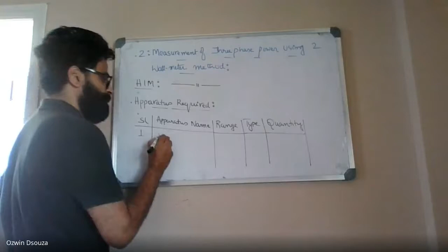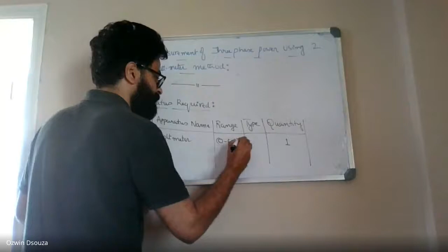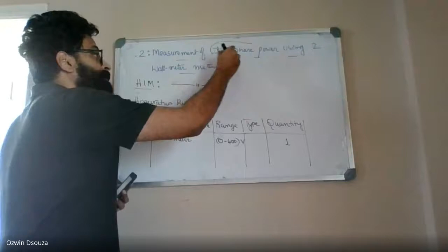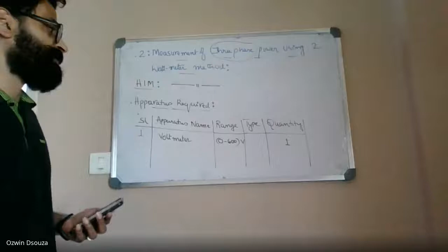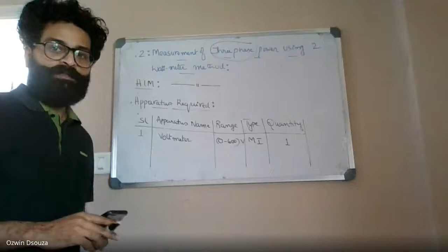So, voltmeter: you would need 1 voltmeter of the range 0 to 600 volts. Why 0 to 600 volts? Because you are connecting to a 3-phase supply, and the magnitude of 3-phase supply is about 415 volts, so the nearest scale value is 600. That's how we select the range: 600 volts, and type is MI, moving iron, because it's an AC instrument.